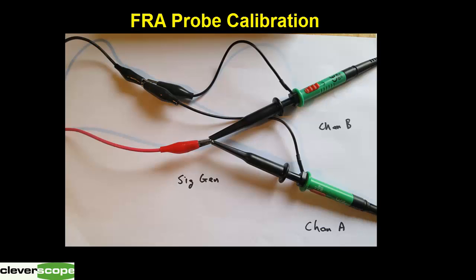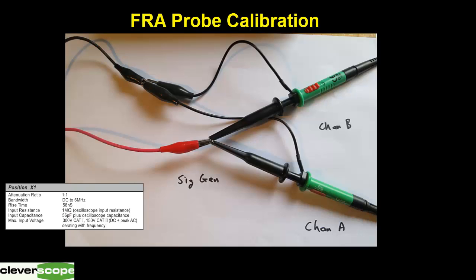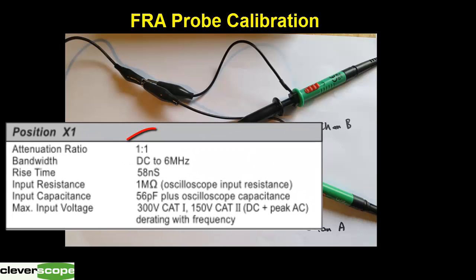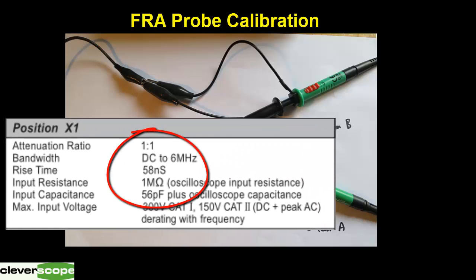Hello, I'm going to tell you about FRA probe calibration. Our standard Cleverscope probes in the 1x switch position have a bandwidth of about 6 MHz. This can be improved to 10 MHz by using probe calibration. In addition, the probe has an input capacitance of about 56 picofarads.